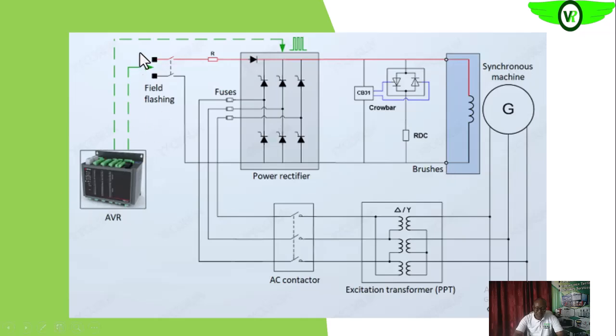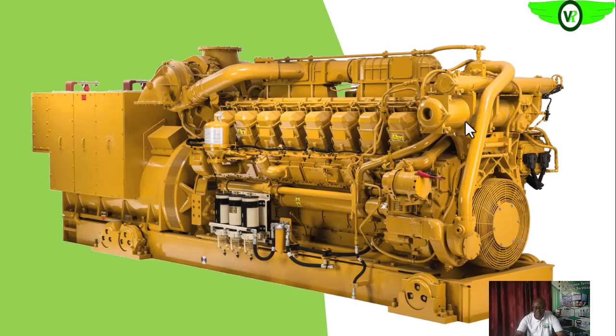Here, this is just for field flashing, in case the main field loses the initial magnetism that is required to build up the voltage within the generator itself. If that happens, you can flash to build the magnetism for the generator to start producing electricity. So everything put together, that is what we are having here: the diesel engine part coupled to the alternator, or the electrical part. So we have a complete unit to produce the power requirement for our facility.